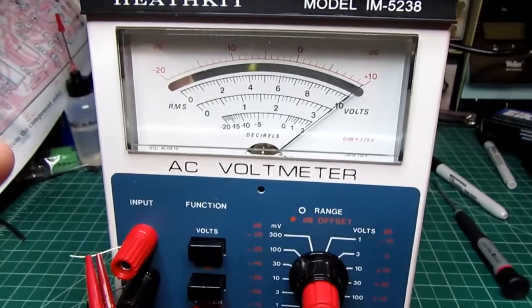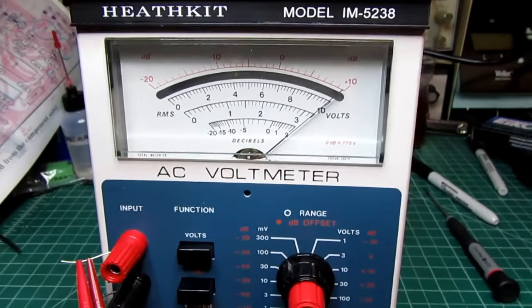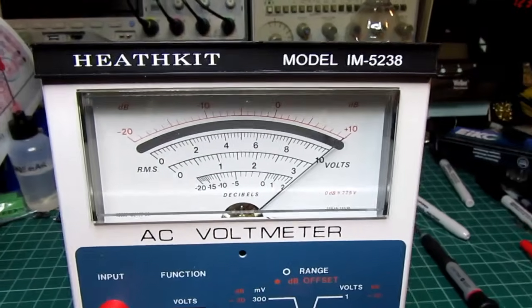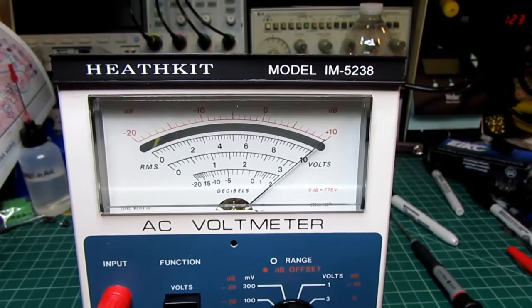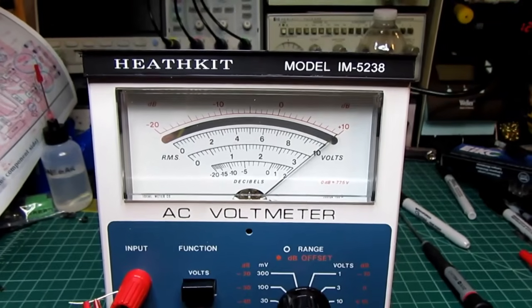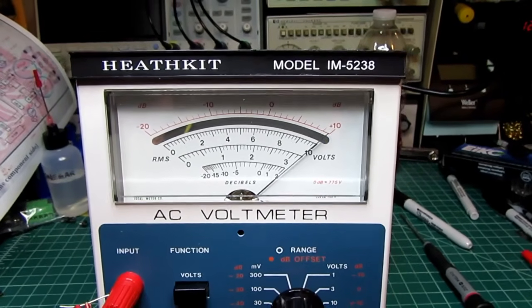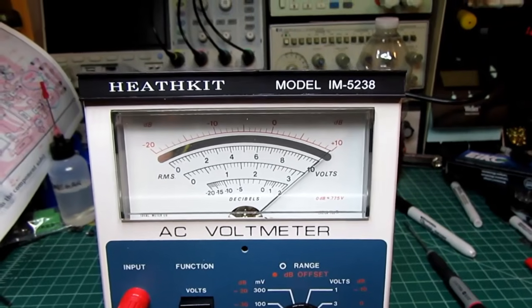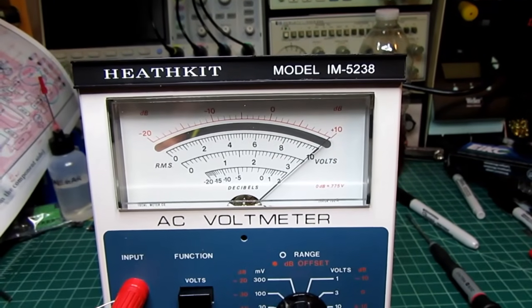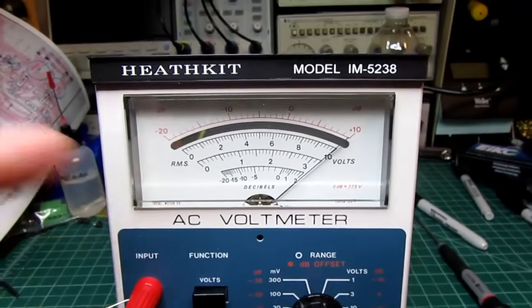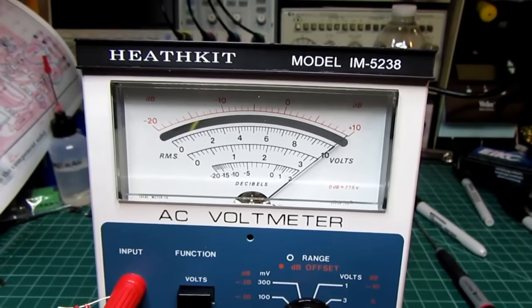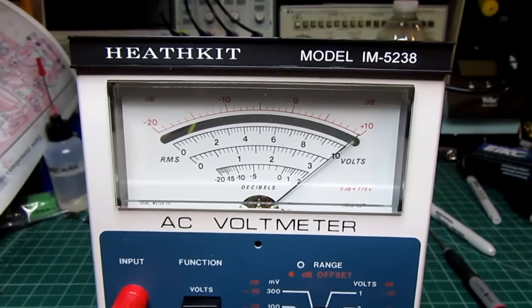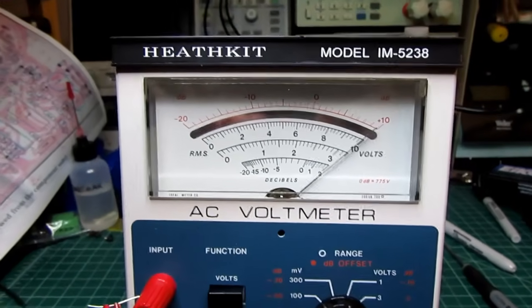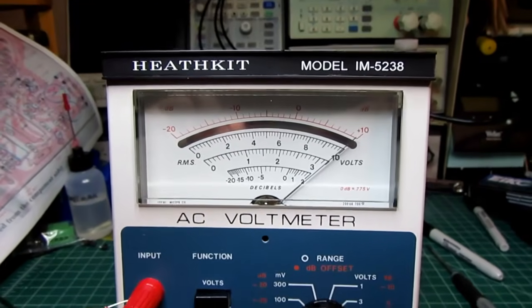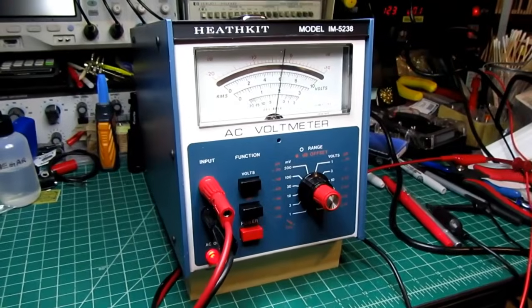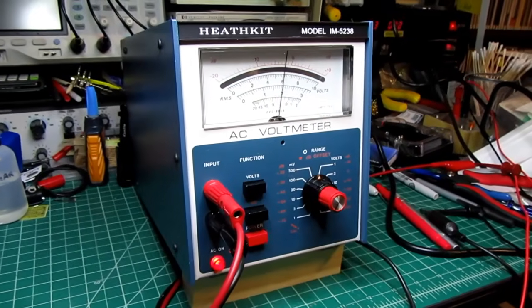I have run through the dB circuit in the calibration procedure, so I know that works, but rather than get into logarithms here, I'm just going to leave the demonstration at this point. The only difference between the two is that the signal runs through the extra dB conversion or logarithmic conversion circuit on the way to the meter movement. And I already know that works, but trying to show you a number without explaining the math, it's not worth the bother. I just know that it works from the calibration procedure. Alright, here's the beauty shot.